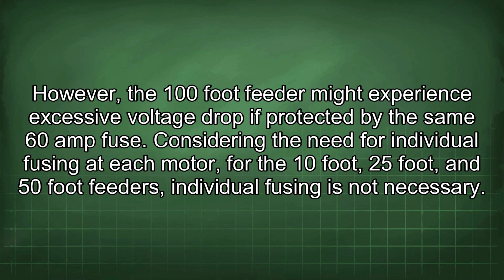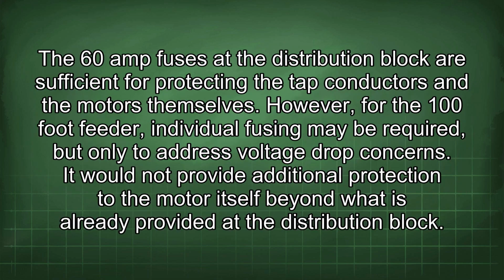Considering the need for individual fusing at each motor, for the 10-foot, 25-foot, and 50-foot feeders, individual fusing is not necessary. The 60 amp fuses at the distribution block are sufficient for protecting the tap conductors and the motors themselves. However, for the 100-foot feeder, individual fusing may be required, but only to address voltage drop concerns. It would not provide additional protection to the motor itself beyond what is already provided at the distribution block.